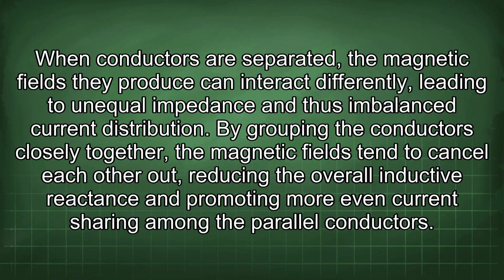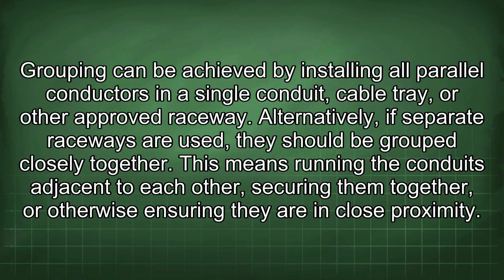thus imbalanced current distribution. By grouping the conductors closely together, the magnetic fields tend to cancel each other out, reducing the overall inductive reactance and promoting more even current sharing among the parallel conductors. Grouping can be achieved by installing all parallel conductors in a single conduit, cable tray, or other approved raceway. Alternatively, if separate raceways are used, they should be grouped closely together.